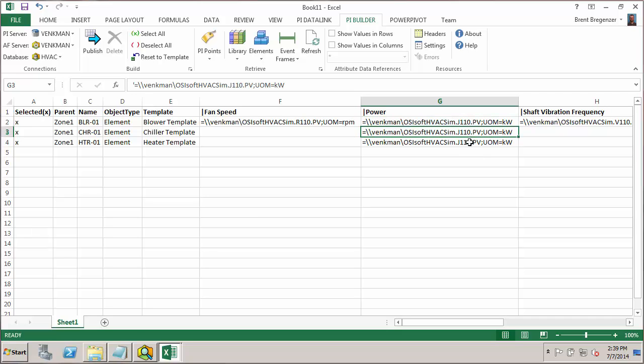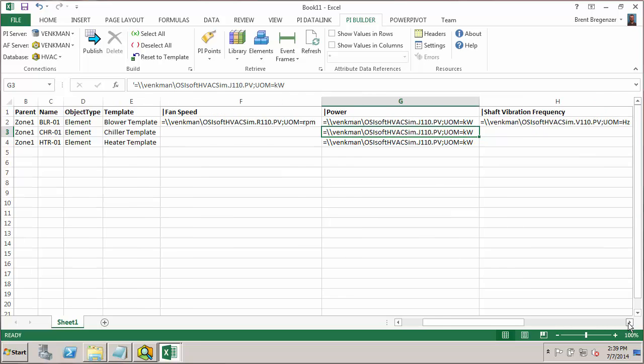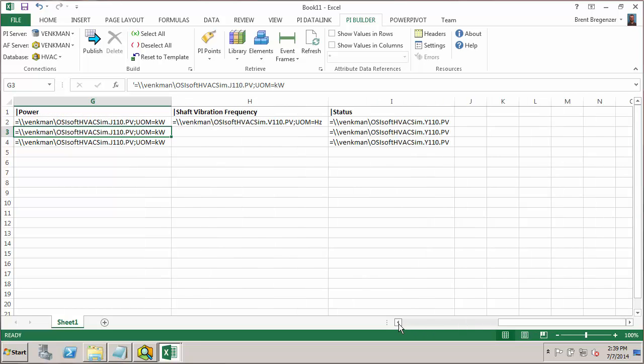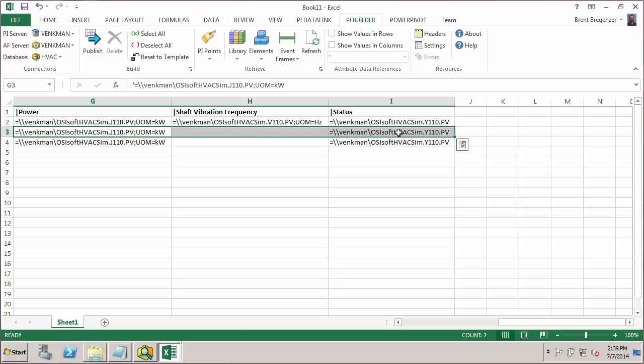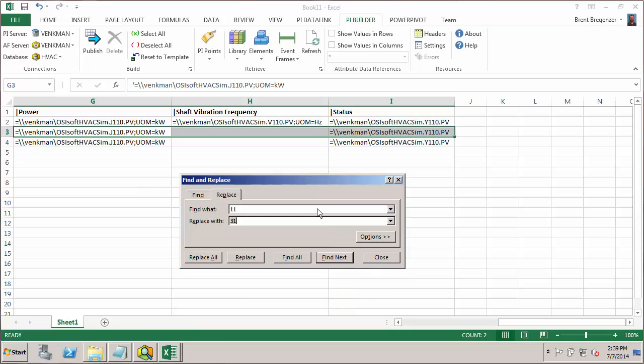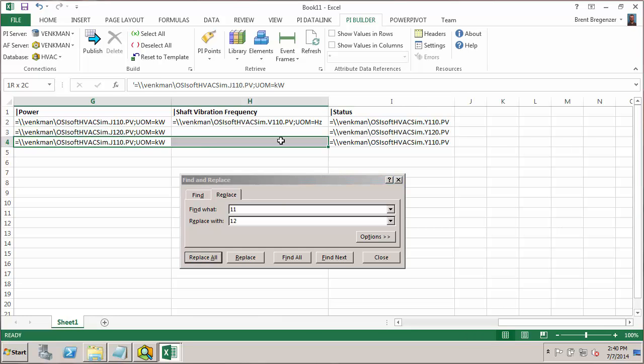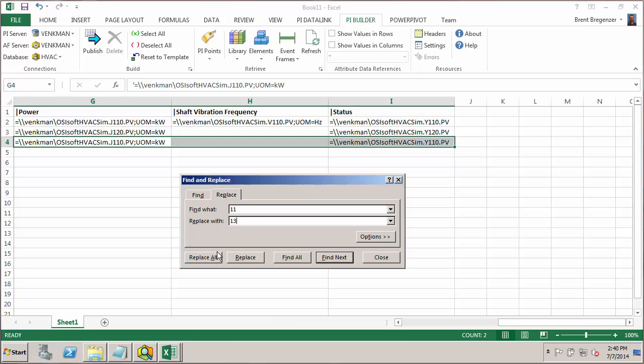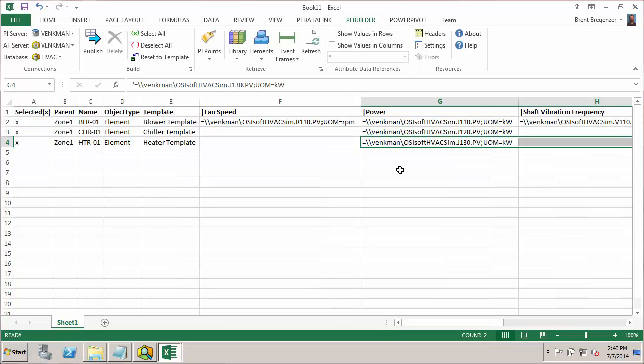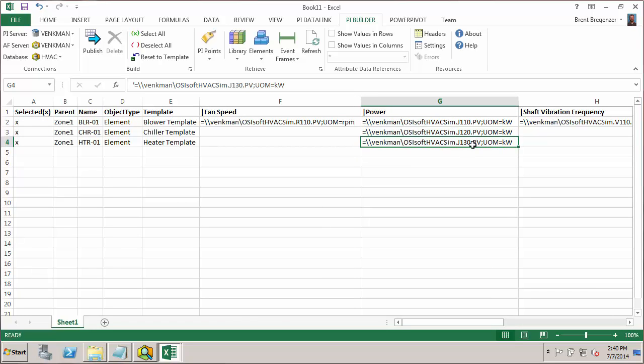From our tag naming convention, we know that the chiller uses a numerical code of 2. So if we just do a control H, which is a find and replace, we can easily just change that 11 to a 12. That changes that second digit to a 2. So I'll just replace all those. And then for the heater, we'll do the same thing, but we'll change from 11 to 13. Replace all those. And now we can see that our chiller is using a J120 tag, and our heater is using a J130 tag. So we have the proper numbering scheme for our chiller and heater tags in zone 1.